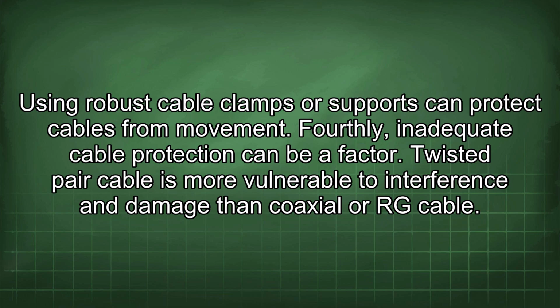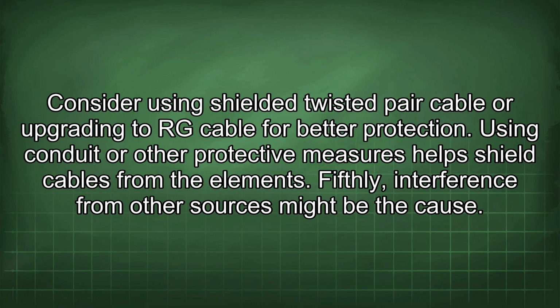Fourthly, inadequate cable protection can be a factor. Twisted pair cable is more vulnerable to interference and damage than coaxial or RG cable. Consider using shielded twisted pair cable or upgrading to RG cable for better protection. Using conduit or other protective measures helps shield cables from the elements.